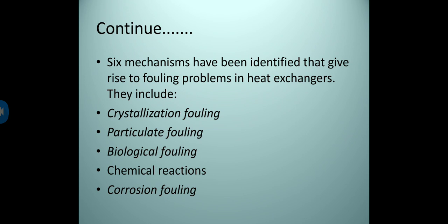Okay. The next one is chemical reactions. The surface may give rise to what is often called chemical reaction fouling. The effect of heat on a process fluid as it passes through the exchanger may accelerate chemical reactions, for example cracking or polymerization reactions that can give rise to deposition on the surface. Right.